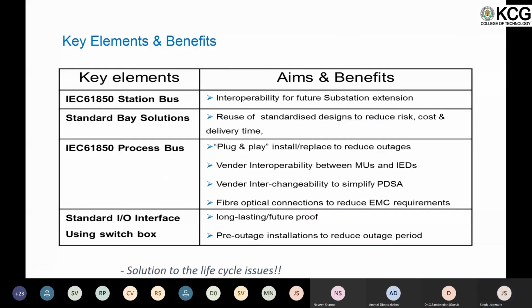And with 61850, as I told, there is interoperability for future substation extension. There is a change of IED itself. And with a standard bay solution, we use standard design to reduce risk, cost, time of design, manpower, etc. With the process bus, you can use plug and play, install, replace, reduce outage. We have vendor interoperability already, then there will be great advantages, PDSA support, post-delivery support. Whole copper wiring is reduced. Now we only have fiber optic running in the substation.